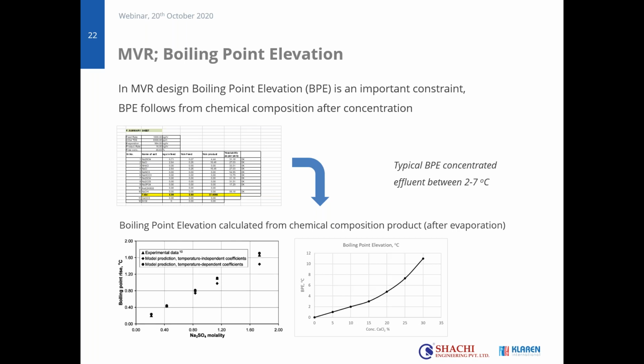Boiling point elevation you can calculate based on the composition of your effluent, but be careful, you need to calculate it for the concentrated liquid, which will run in your evaporator. There are methods available also within Shachi to calculate this boiling point elevation. And if you are not absolutely sure about your composition, another way is just doing the concentration in a lab and measuring the moment it starts to boil. In the bottom pictures, you see two different salts, sodium sulfate and calcium chloride. You can see that for calcium chloride, at high concentration, this boiling point elevation really can become substantial. That means it's really important to consider this, because I will show you that in the next slides.